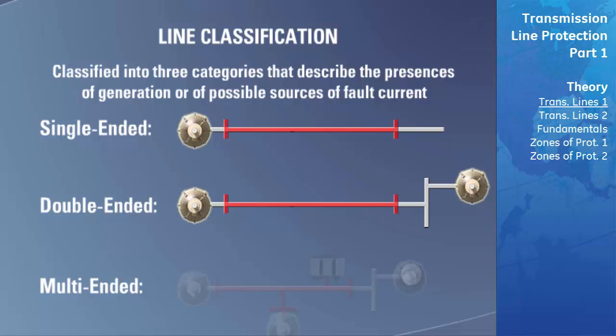A multi-ended line has more than two boundaries, each of which can have a source of fault current available. At the time of a transmission line fault on this type of line, the direction of normal power flow can be highly variable and the fault will be fed from many different locations. Sometimes the transmission line itself will be tapped to provide a source of power to a load. Distance protection is one method of protecting a transmission line in this configuration and will be covered in detail later in this section.